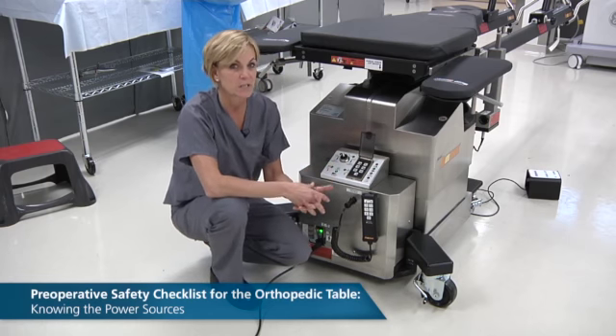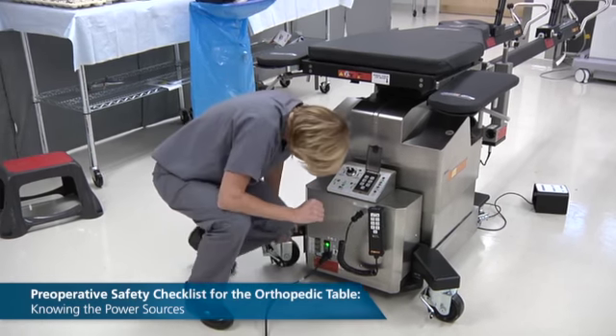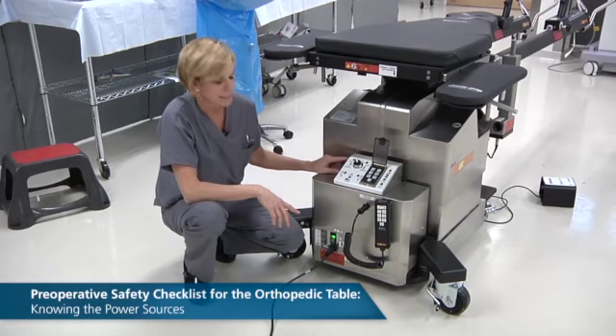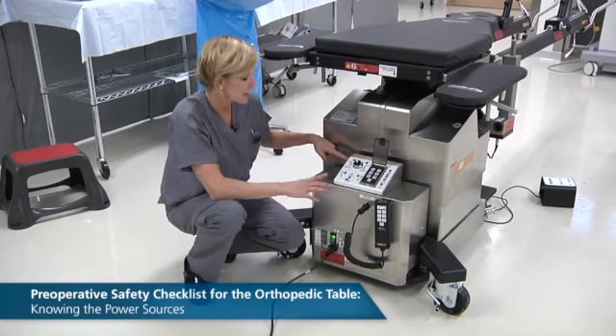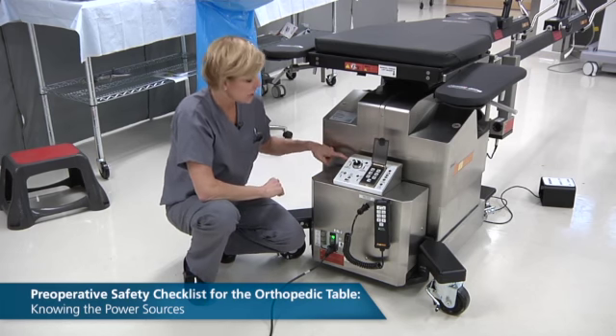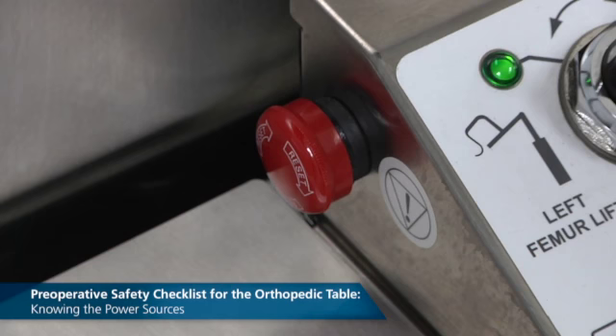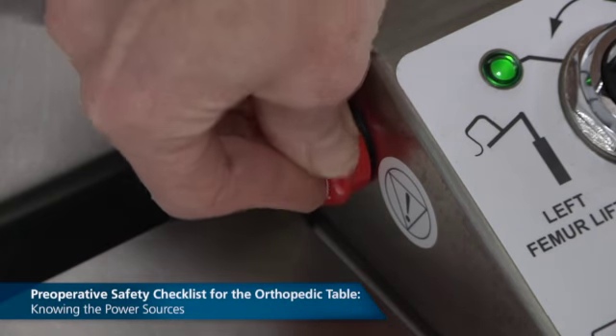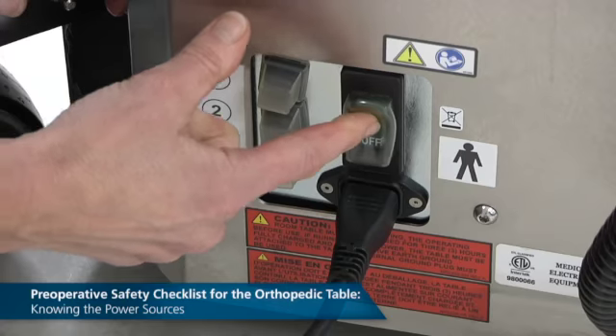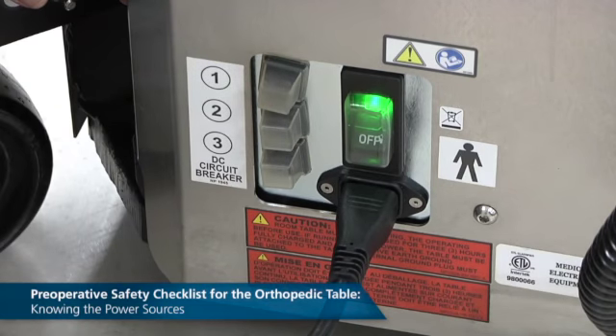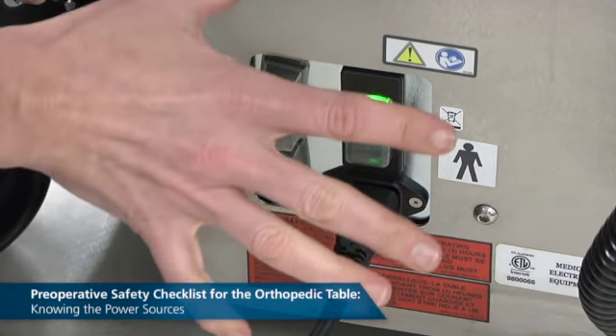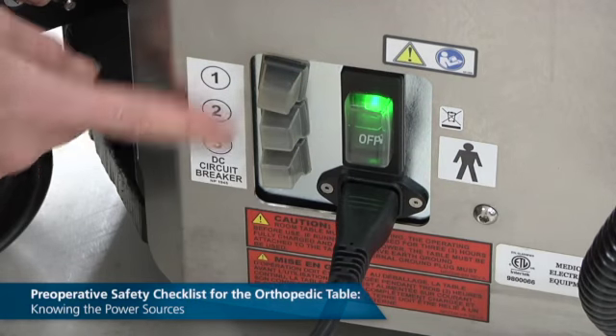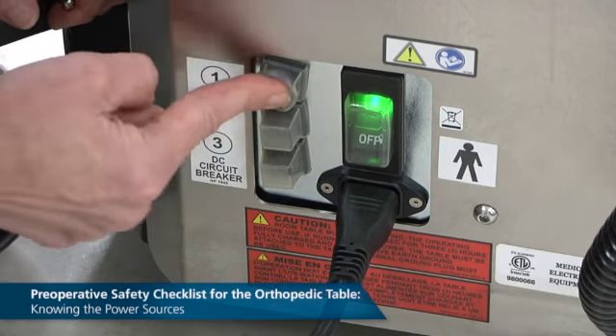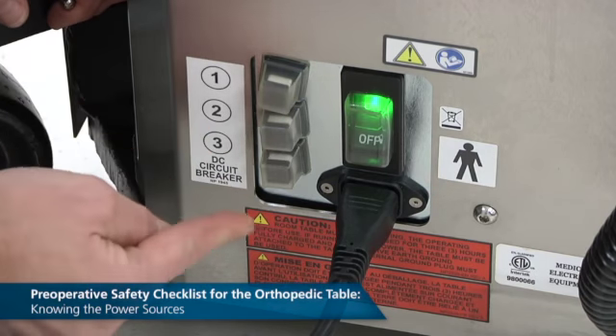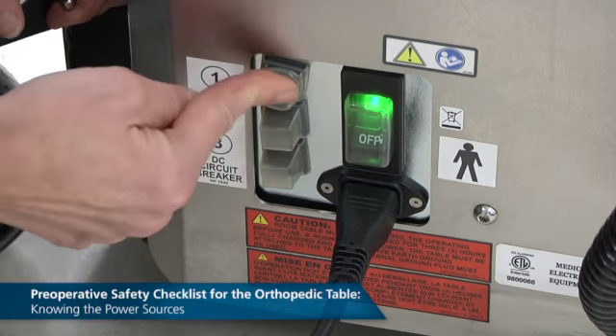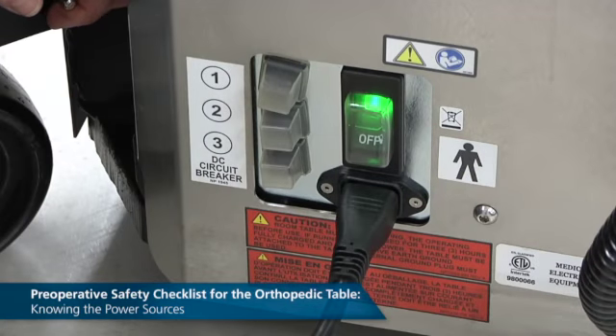What you want to do in this case is reset the table. Now, there are lots of ways to do that, but what I'd advise is recognizing that there's a red button here on the side of the control panel. The red button says reset. What you would do in this case is push the reset button, turn it to the side, and the table can be turned on. Now, if the reset option and just unplugging and plugging back in the table doesn't work, there are 3 circuit breakers here to the left. Pushing each of them and then re-pushing them should restore power to the entire base of the table.